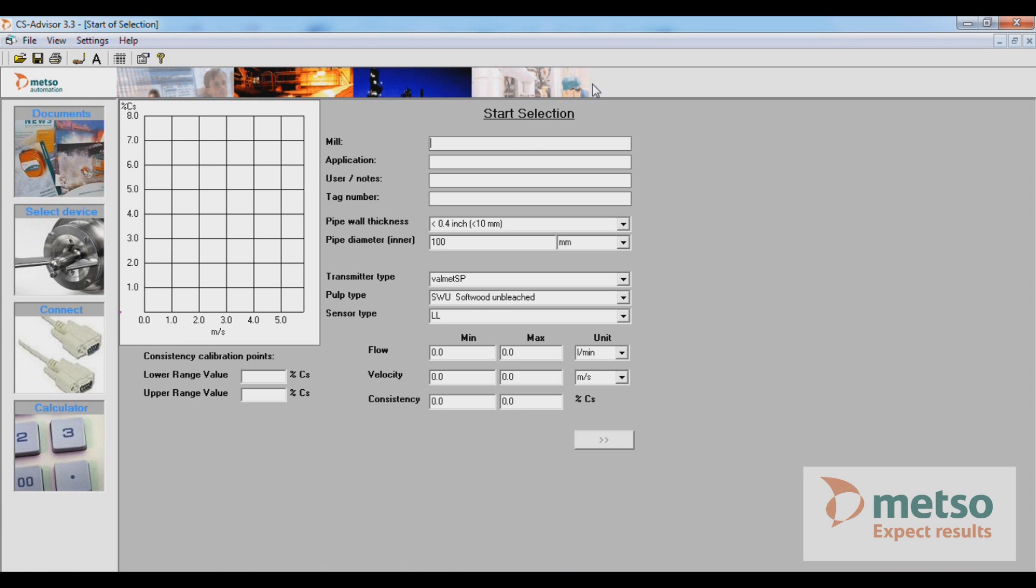The SmartPulp requires laminar or plug flow, which requires a certain amount of straight pipe. To determine straight pipe requirements, you can use Metso's CS Advisor software. And here, we're going to go ahead and begin completing the CS Advisor software to determine the straight pipe requirements.